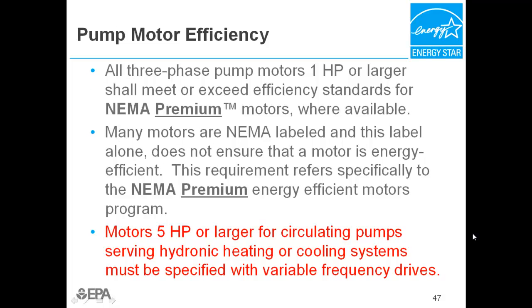Pump motor efficiency. The program prerequisite requires that 3-phase pump motors, 1 horsepower or larger, shall meet or exceed efficiency standards for NEMA premium motors, where available. Single-phase pump motors or pump motors smaller than 1 horsepower do not need to meet this prerequisite. This requirement is the same for the prescriptive path and refers specifically to the NEMA Premium Energy Efficient Motors program.